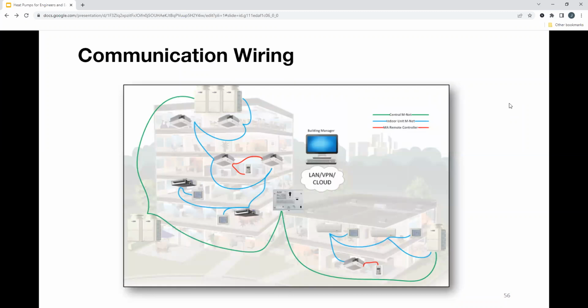And this is just a diagram showing you your communication wiring, right? So your central system, your outdoor units are connected to a central controller. And then from each condenser, you have communication wire daisy chained down throughout the building. And if I tapped into the outdoor unit, I could see what's happening in every zone. If I tapped into this local controller right here, I could see exactly what the condenser is doing. Everything is built in and has its logic built in.